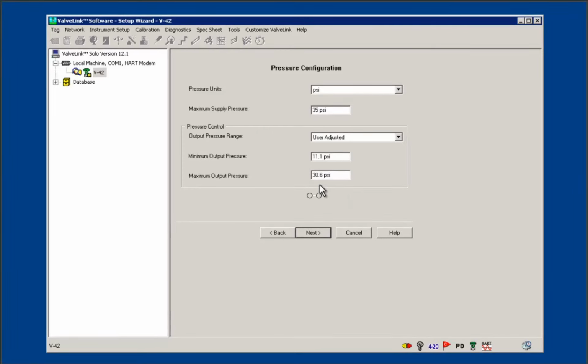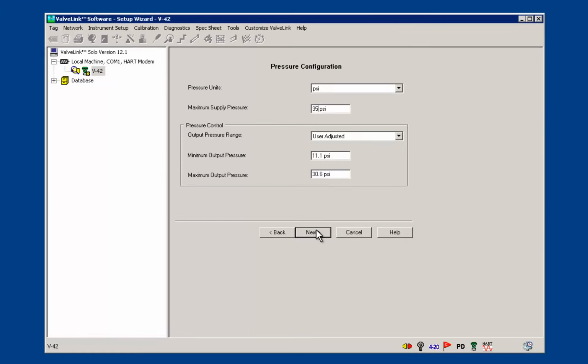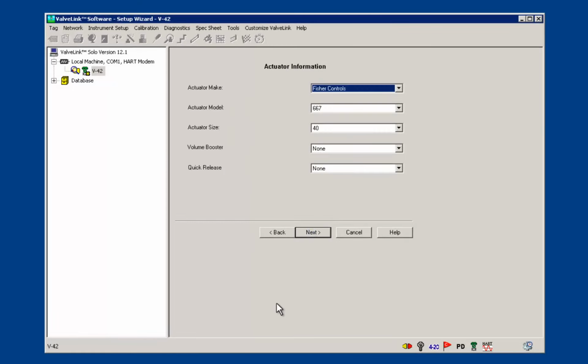Set your maximum supply pressure by looking at the pressure gauges on the DVC6200 digital valve controller or the plate on your actuator. This instrument's maximum supply is 35 psi. Since I chose a control option of fallback on sensor failure or deviation, I don't need to change the pressure control options because they will be set later during the automatic calibration procedure. Click Next.